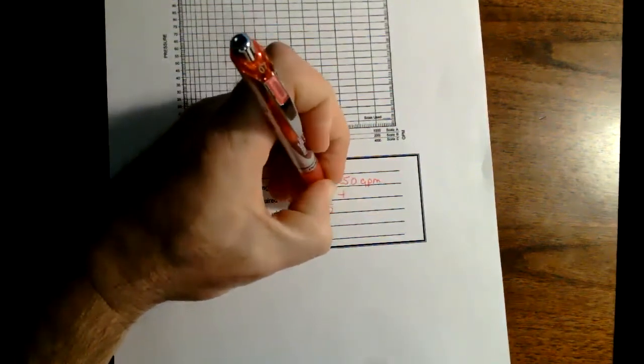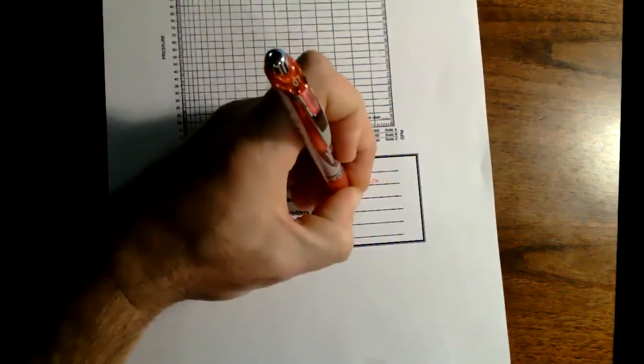I'll put that in here because that is the minimum amount we can put due to the NFPA standards, right? Okay, and that was in your reading and text as well, so don't worry about that. It is in there. Hopefully you guys caught that. So even though when we reduced it with the sprinkler system down to the 812 gallons per minute, the minimum we can do is 1,500. So that's all we can do.